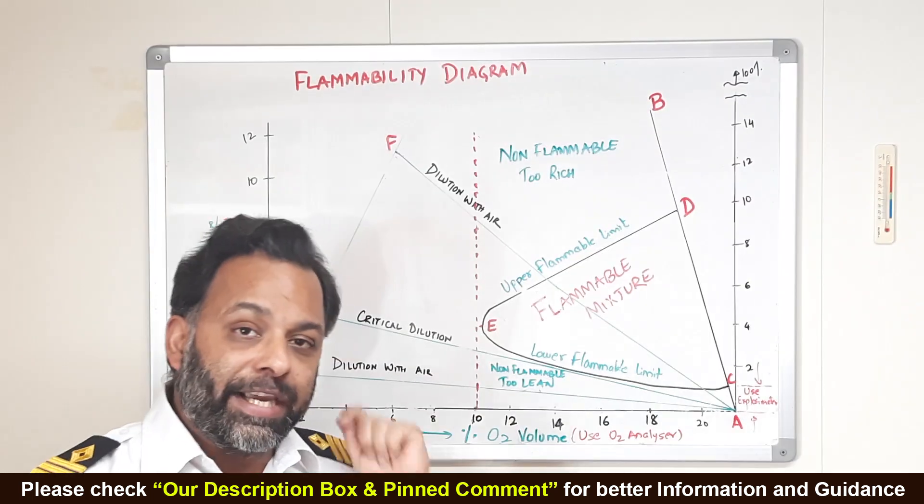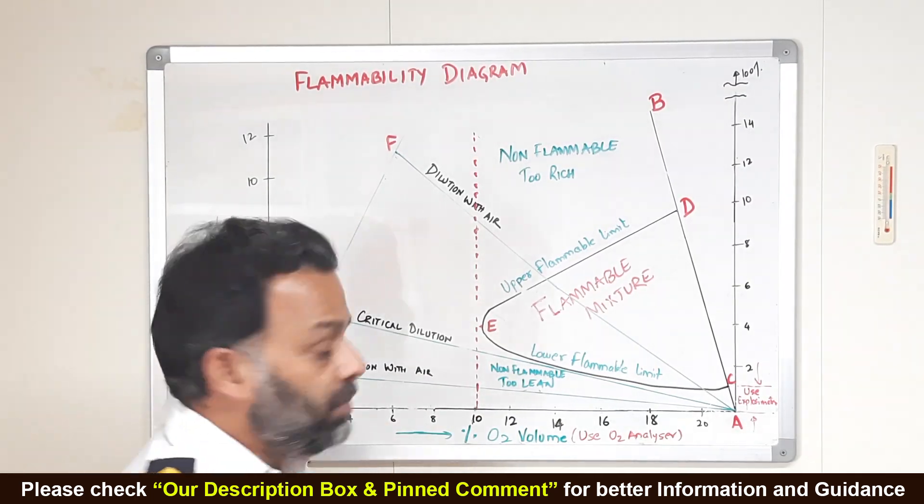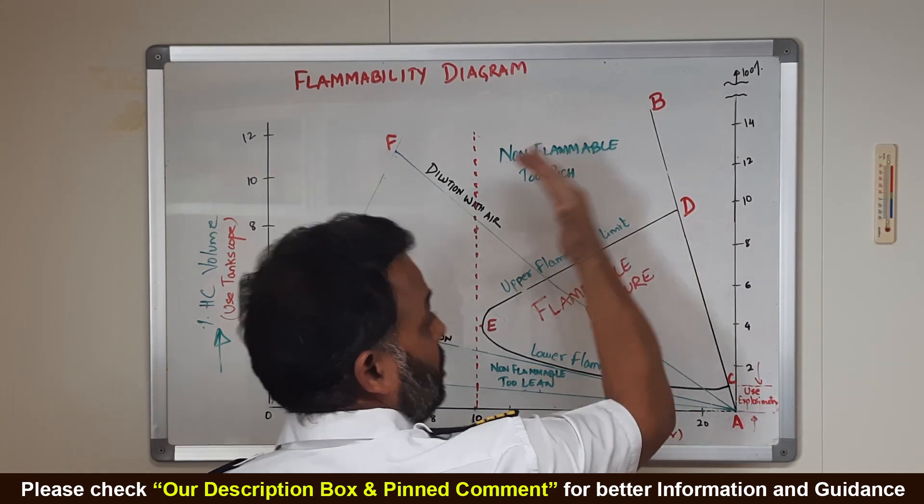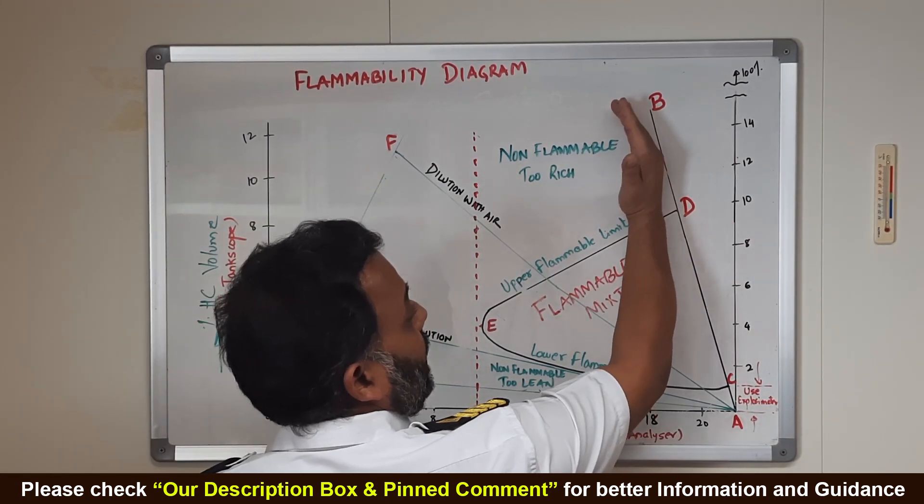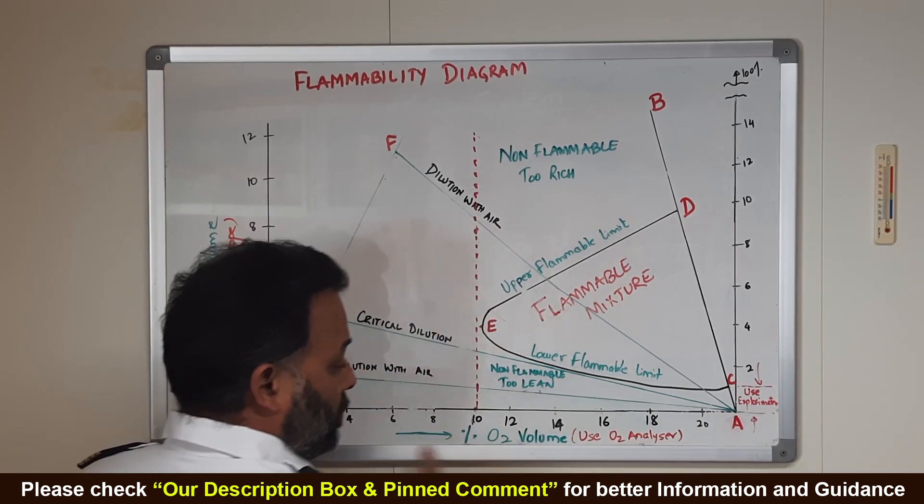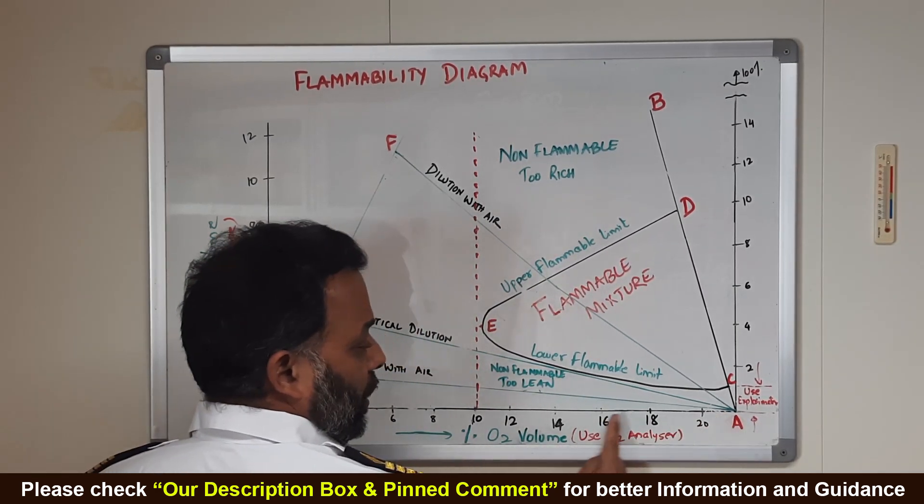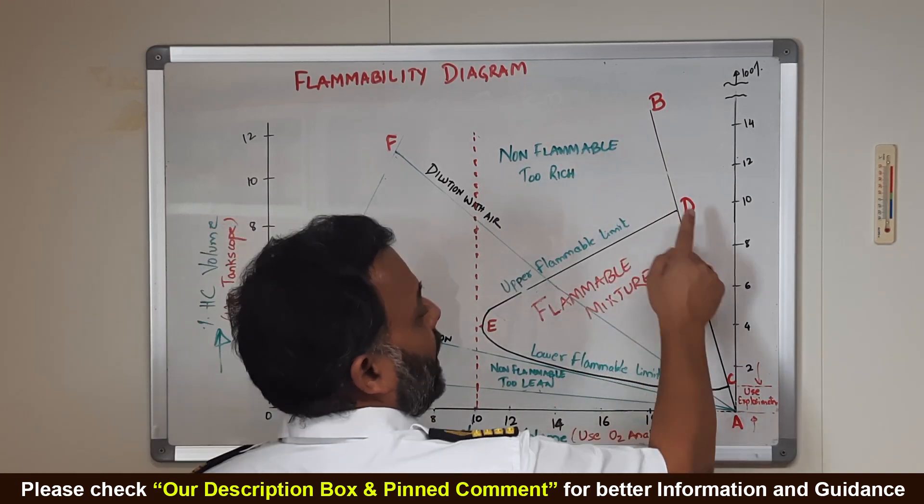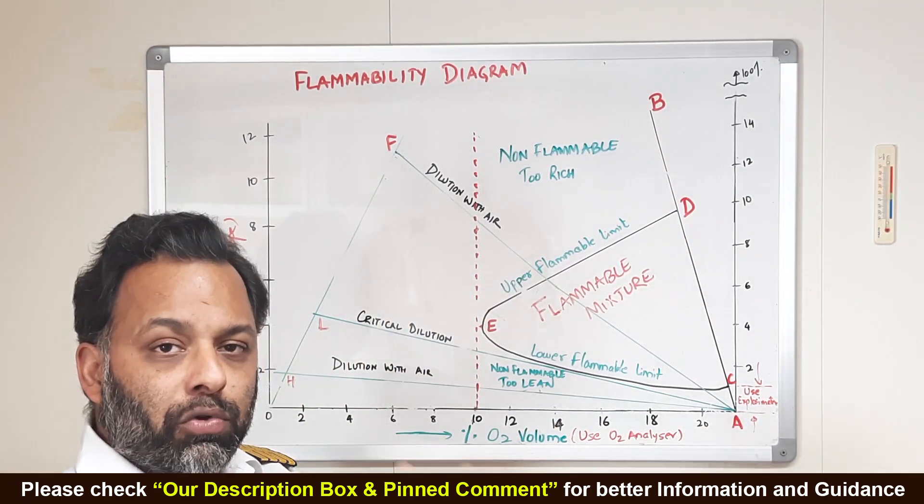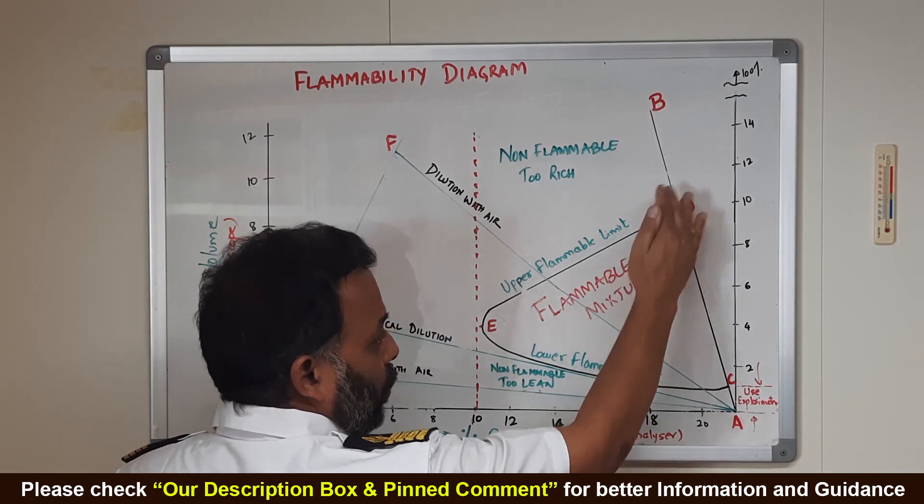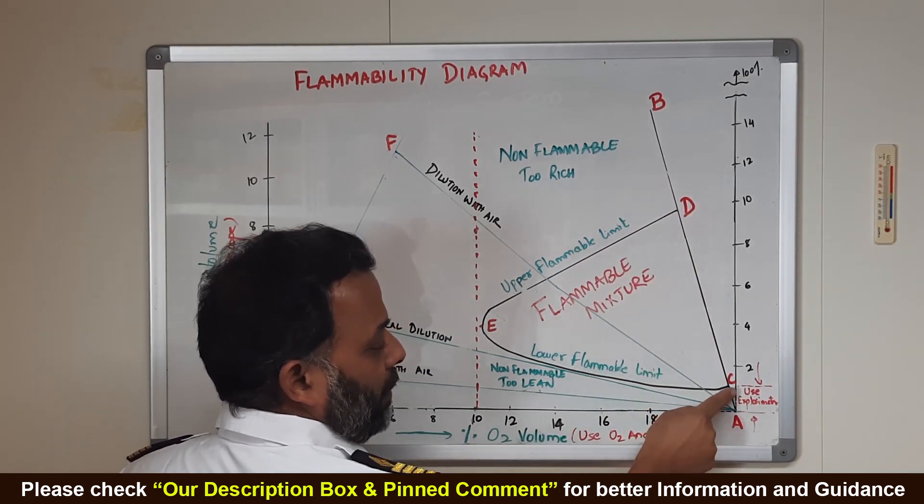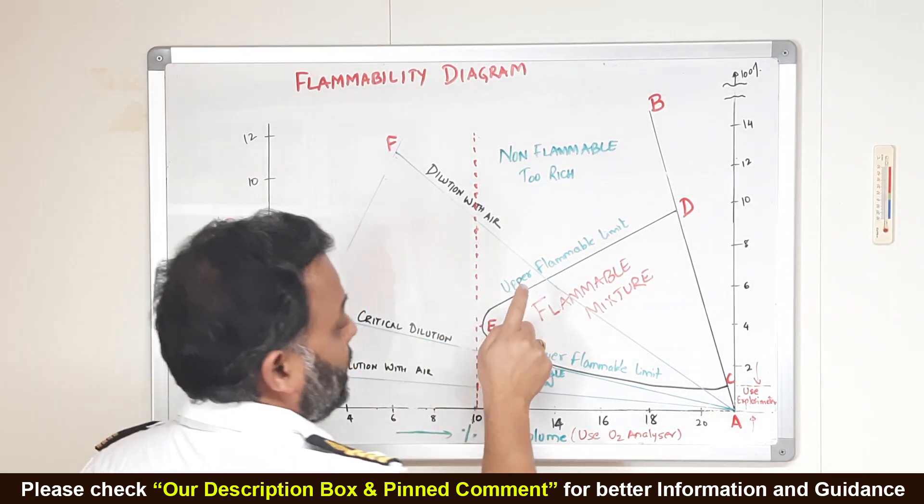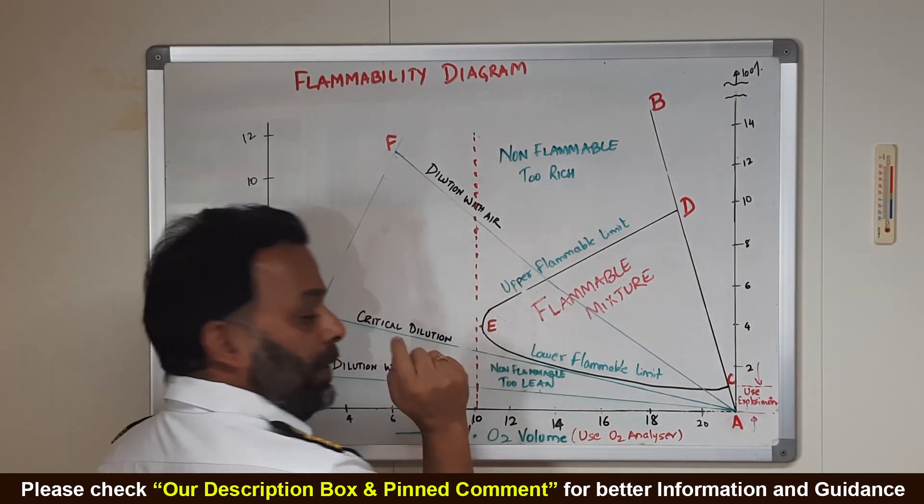Now, as we introduce IG, inert gas into the system, this line will start to move on the left side. As we introduce more inert gas into the system, this oxygen will start going down. As we introduce more inert gas, this upper flammable limit will go down and this lower flammable limit will come up. And there will come a point, point E, where the UFL and the LFL will meet.